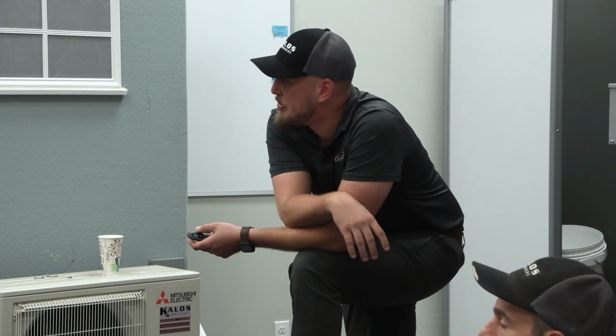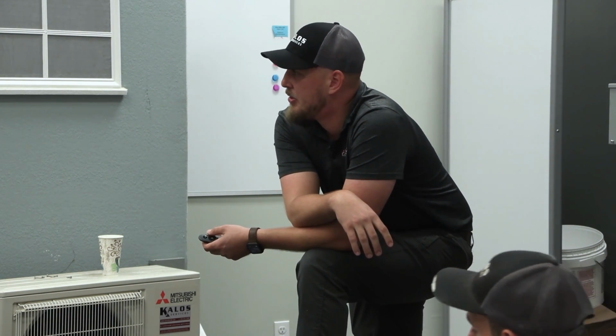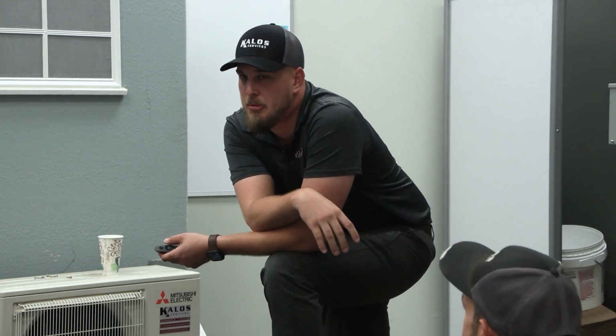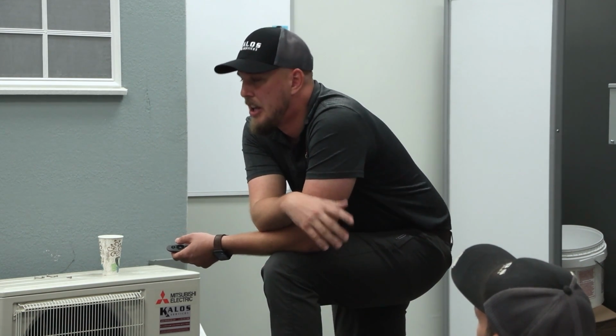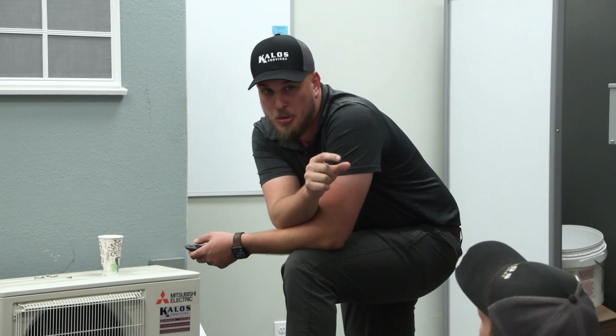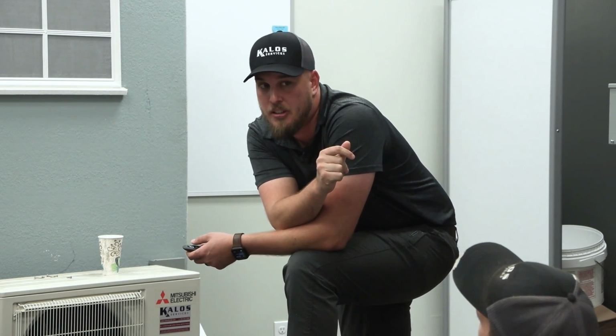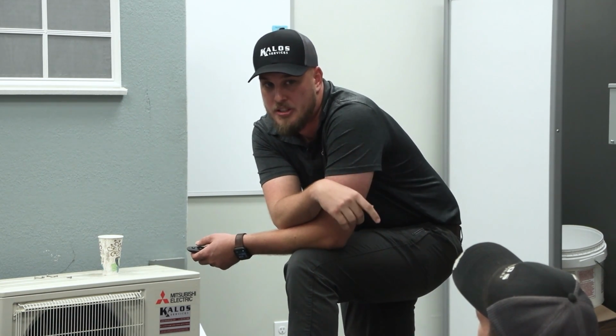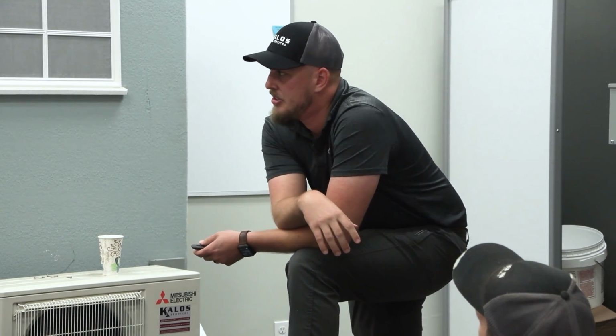Yep. Many service calls where we've gone out for something leaking and we haven't been able to pinpoint exactly what's leaking. Is it the pump that's failing? Is it a connection point? A lot of the time, it's just a small section of something that's getting to dew point and condensating water. And it doesn't happen right away. A lot of these leaks happen over hours of runtime. So if you're in that position, keep that in the back of your mind: condensation.